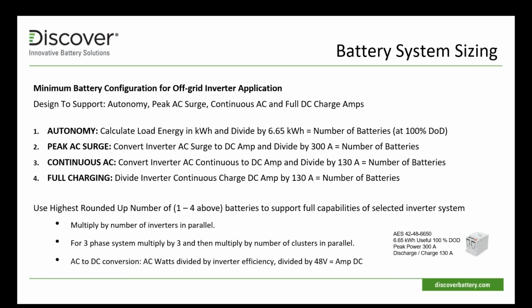This is outlined in application notes that we publish regarding integration with inverter chargers, and we're including more and more of this information. If you don't size the battery system to its full capability, if it's just there on the edge, the system will probably work just fine. Derating of some of the system capabilities may be necessary to fit it in. There are other ways of accommodating this, as this sizing looks at the full peak capabilities.